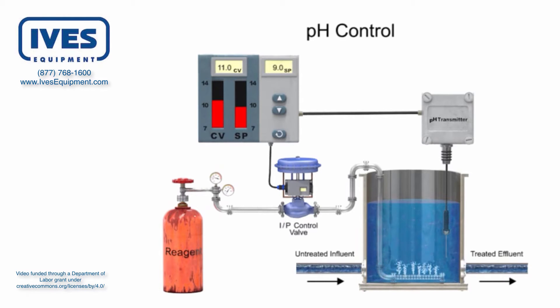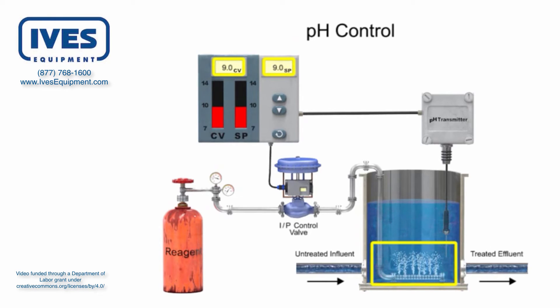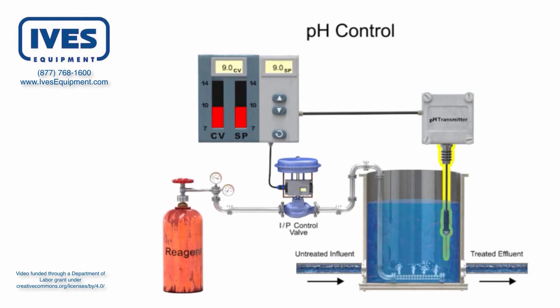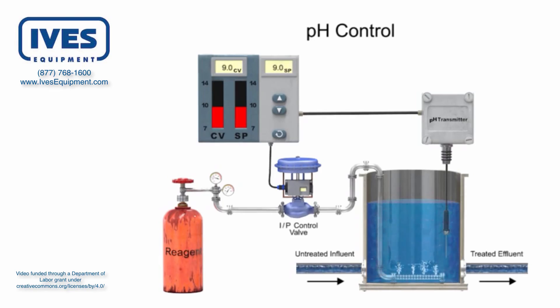As the increased carbon dioxide mixes with the influent, the pH is lowered in a controlled manner. Reaching the setpoint, the carbon dioxide flow is minimized and the process is continually monitored for variation. The effluent is the treated water that is discharged out of the tank. The process continues to provide the lime-softened water at the desired pH level.